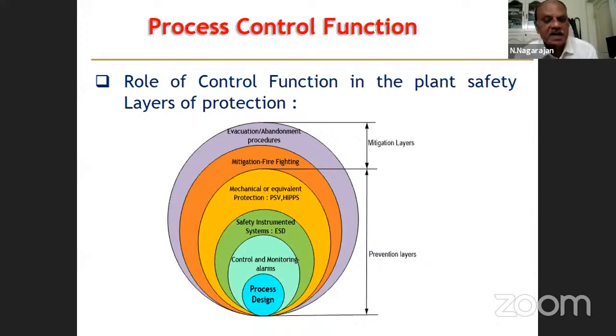HIPPS is high integrity pressure protection system. So these are the safety layers. Suppose even after all these precautions, the safety systems, devices, if something happens and fire occurs in the plant, then the next is the mitigation layer. Mitigation is the incident has occurred. We have to effectively control and contain the hazard. That is the mitigation measure.